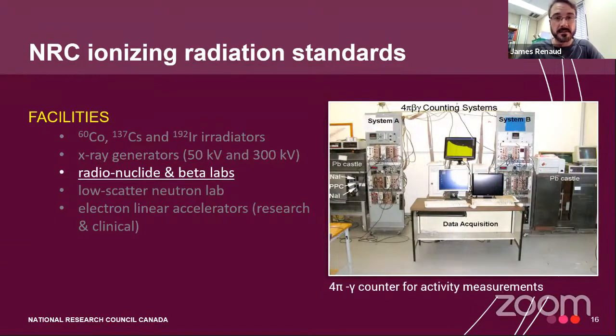The radionuclide metrology facilities consist of radiochemistry and decay counting labs. Some of the facilities implement 4-pi beta gamma, as well as the liquid scintillation counting primary methods, as well as a suite of secondary measurement detectors, radionuclide calibrators, solid state detectors, alpha spectrometry, etc. In the beta lab, 2 beta irradiators can be fitted with promethium, krypton, strontium sources, which can have a mean energy anywhere from 70 to 670 keV. And they generate absorbed dose rates anywhere from 1 to 1,000 milligray per hour. These rates are established with our primary standard setup, which is based on extrapolation chamber measurements. And the irradiators are used for quality assurance testing of personal dosimetry systems and calibrating beta survey meters.